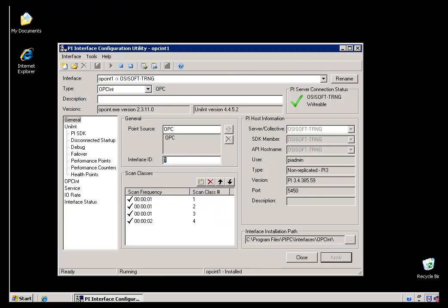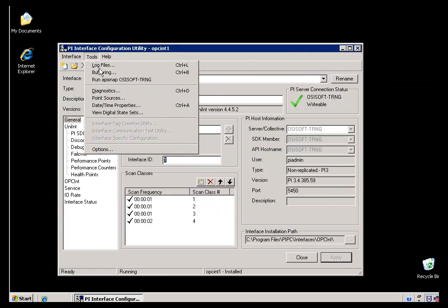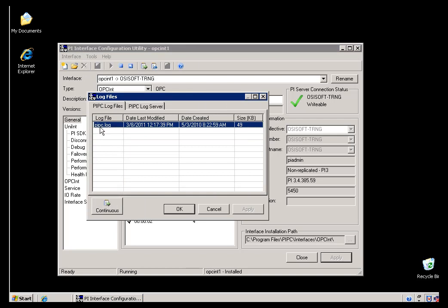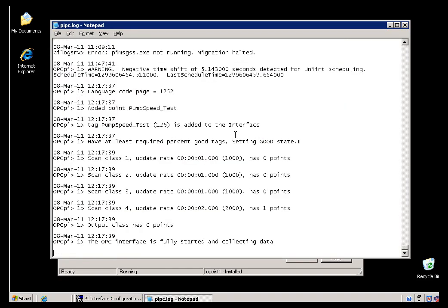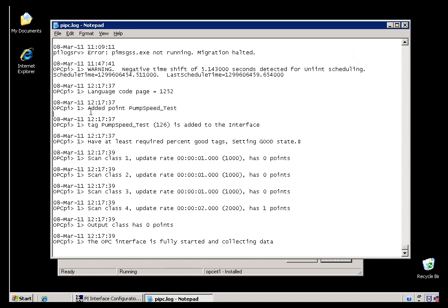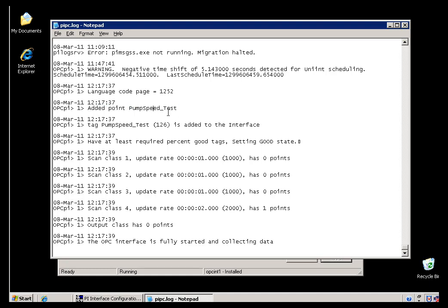The real test is, let's go back to the Interface node, let's look at that PIPC.log again, and let's take a look to see if the Interface has said anything about this in the log file. Right here, I can see that, just a couple of seconds ago, the Interface reported that it added that point, PumpSpeed Test. It's added that to the Collection duties of this Interface, and it looks like everything is going okay now.